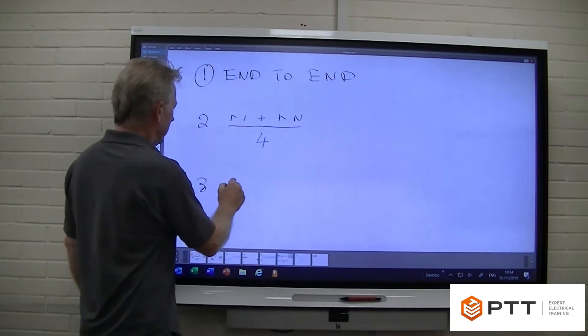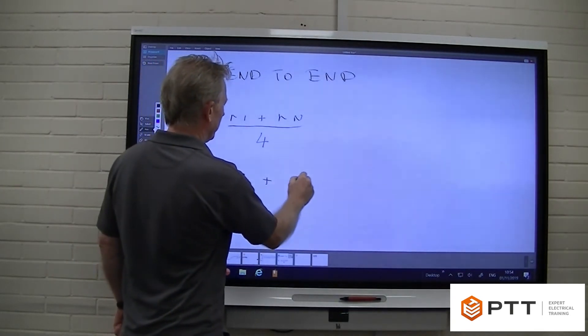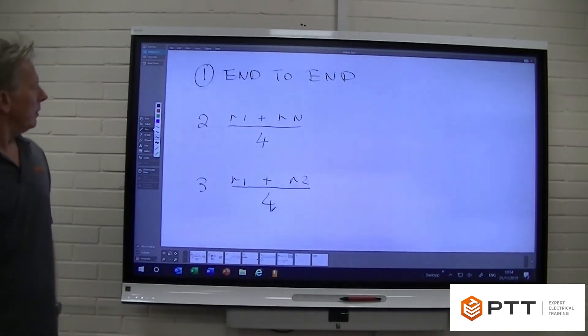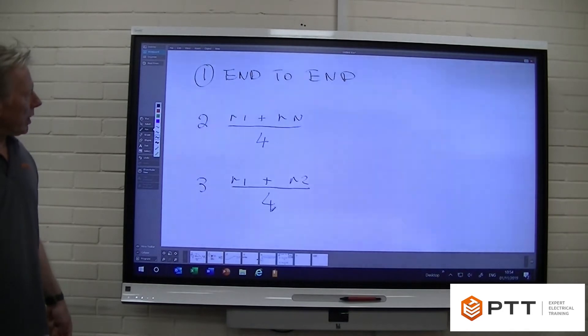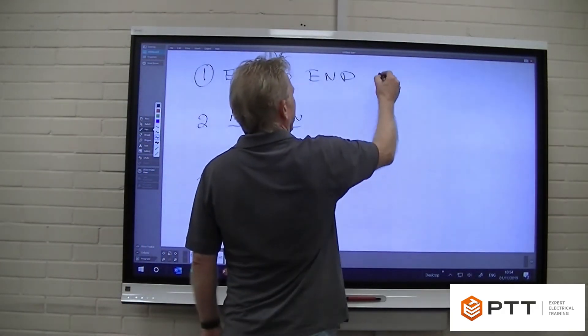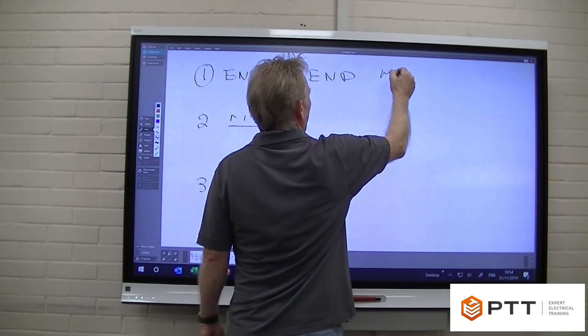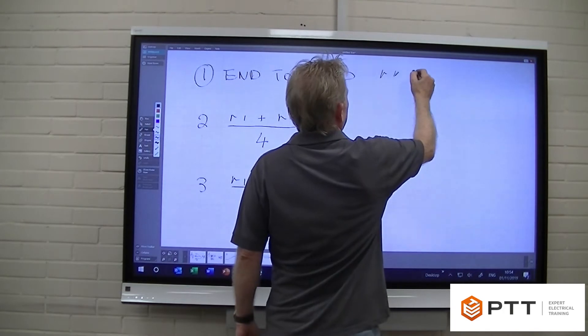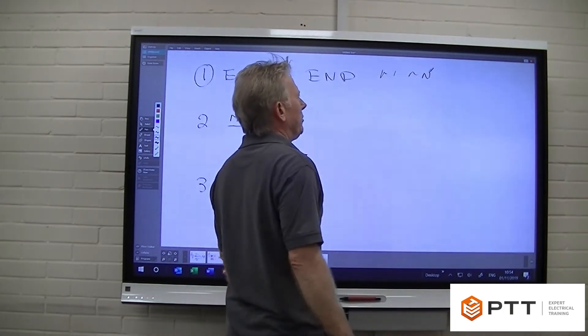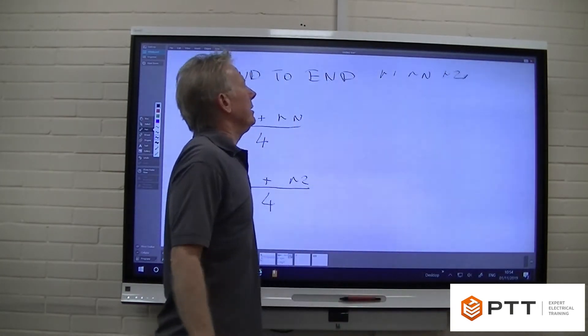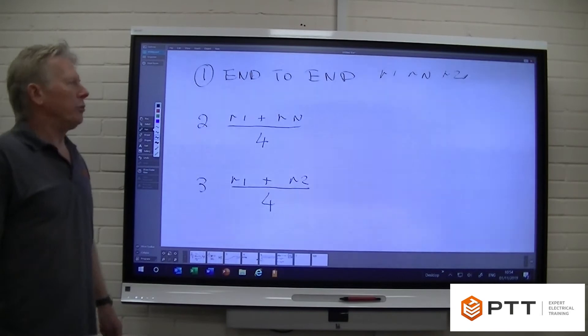The third test is little r1 plus little r2. We're going to divide that by four, and then we're going to make a cross connection and test that. So what is this little r1 and little rn? Well, that is actually the results from the first test, because what we end up with here is little r1 – that's end-to-end with our line conductor – little rn, which is end-to-end with our neutral conductor, and little r2, which is end-to-end of our actual CPC.